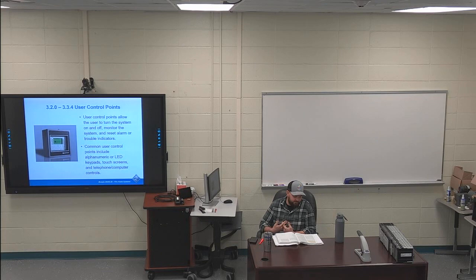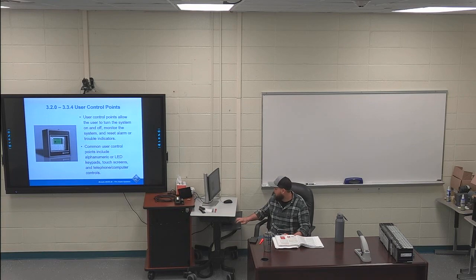Last paragraph in that section before 3.3. First sentence is highlighted. Verification is commonly used in hotels, motels, hospitals, and other institutions with large numbers of detectors. It may also be used in monitored fire alarm systems for household to reduce fire or false alarms. So you can use verification to make sure that there's actually a fire, there's a lot of smoke or something like that before sending in all the fire department and stuff like that. You got 3 questions on page 27 for section 3 review, and then I'm going to move on to section 4.